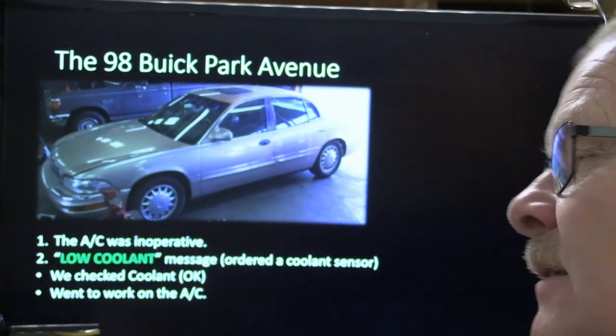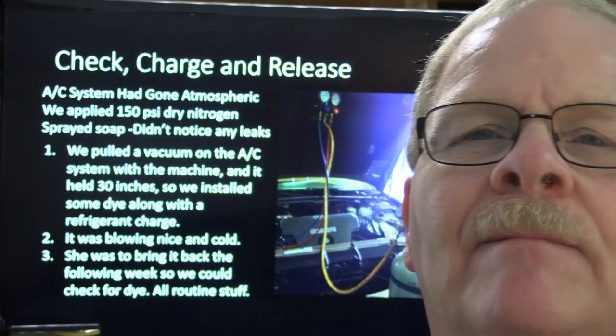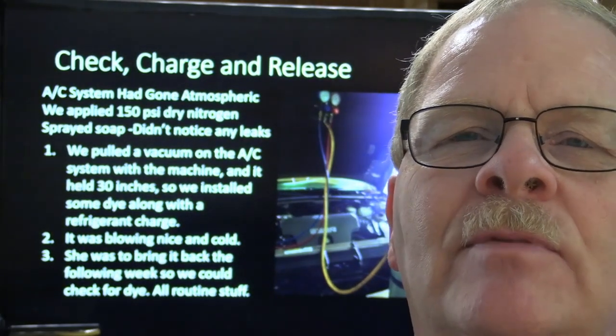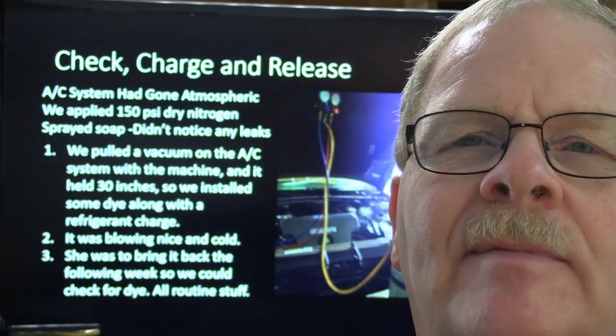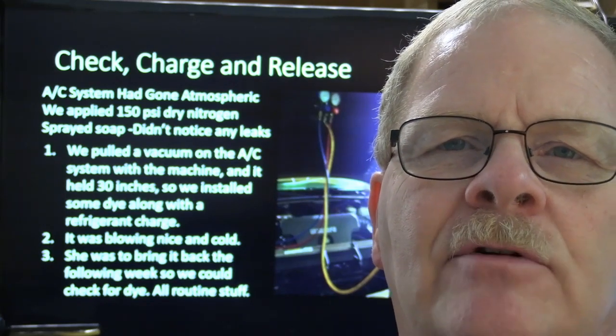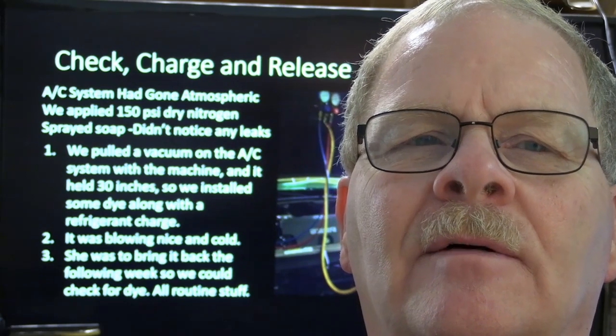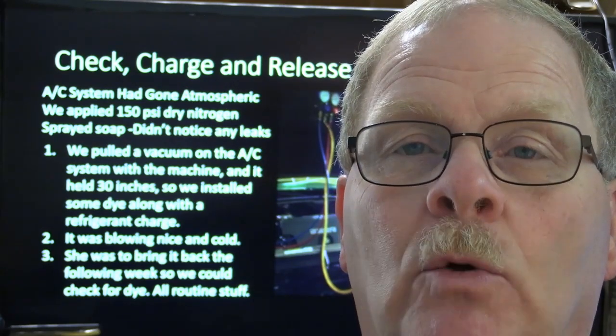They didn't have one in stock, so we went right to work on the AC. We put some nitrogen in there, about 150 psi. If you put too much of the dry nitrogen in there—too much pressure—you'll basically make a leak where there is no leak.